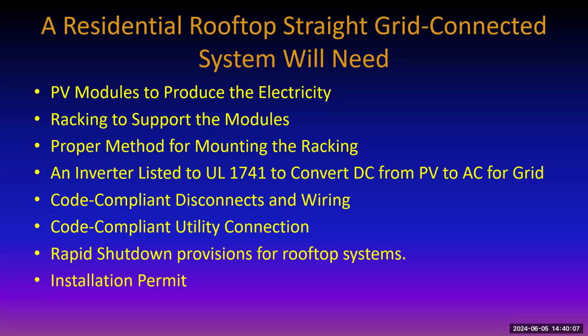You need a permit, unless you're way back in the woods someplace doing a non-grid connected system. But otherwise, you're going to have to get a permit. That's fun. Generally it takes about as long to get a permit as to get the thing designed. Maybe longer, depends. And you're going to have to sign an agreement with the utility that if they want to turn off your system for whatever reason, they can come and do that. But otherwise, they will pay you a certain amount for whatever electricity is delivered to them upon being connected. So that's the leading up to the installation. These are things that you need to be accumulating and getting straightened out.